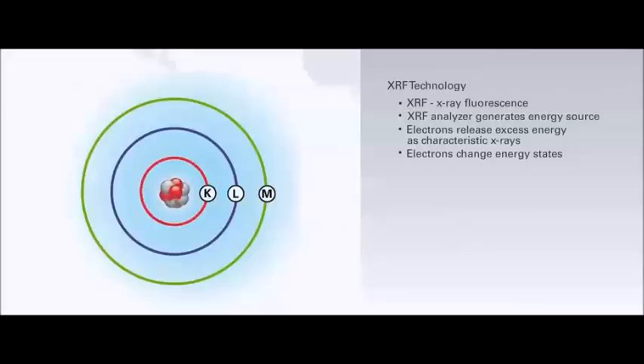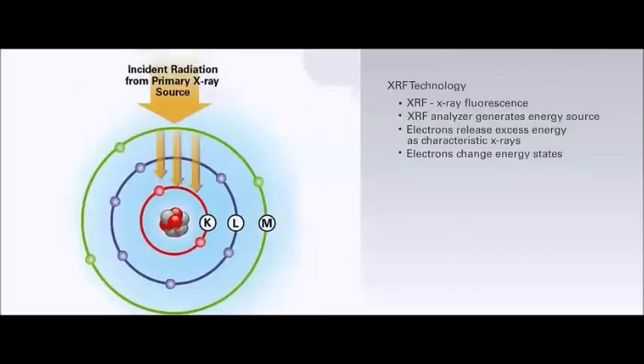For elements heavier than neon that contain three or more orbital shells, the three lowest potential energy orbital shells are the K shell, L shell, and M shell. When a sample is radiated by sufficiently high-energy photons generated either by a miniature x-ray tube or a sealed radioisotope source in the analyzer, electrons from the inner orbital shells of sample atoms are ejected.